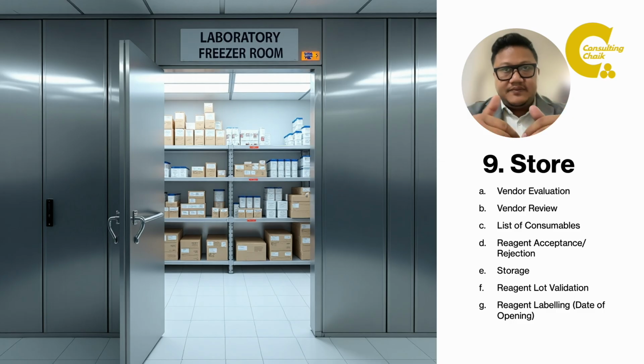And the second aspect is to compare the new and old reagent with the same patient samples. You can use the last three samples where you had used the old reagent and compare them with the new reagent, where you run the same last three patient samples. And after comparing, you know whether to accept or reject that lot. If the reagent lot is the same, you don't need to do this exercise.